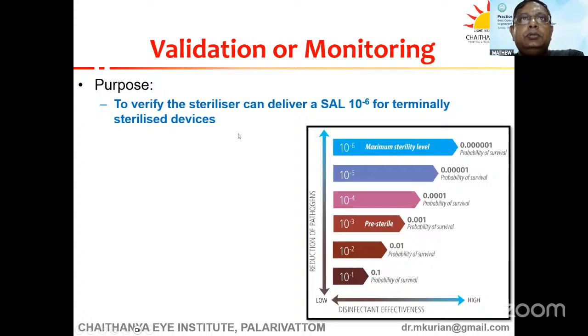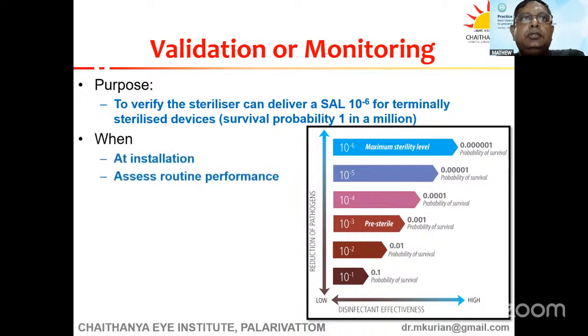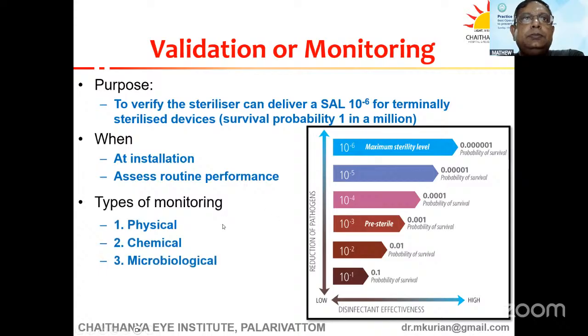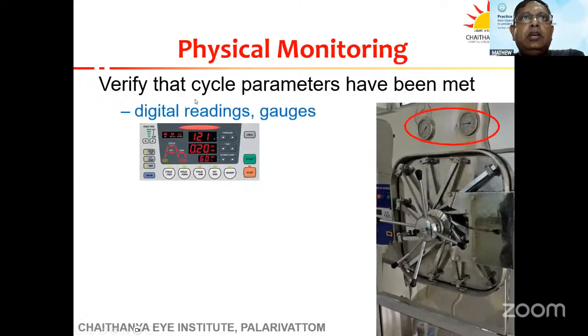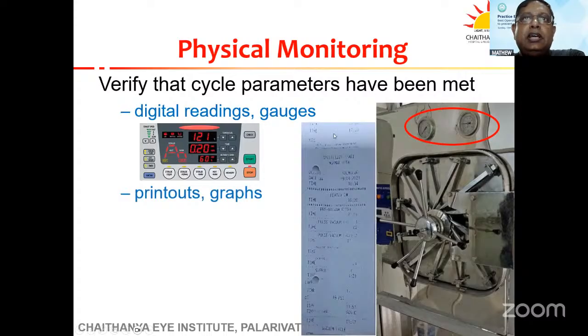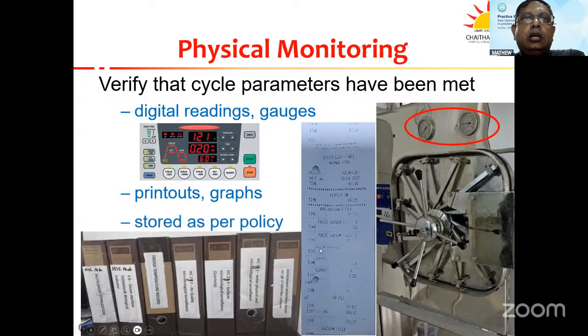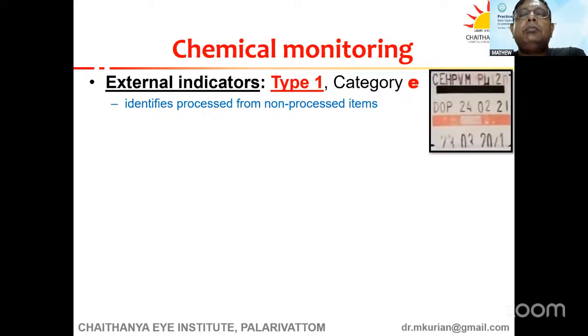In validation, what we are trying to do is to monitor that what we are hoping to do is actually achieved, and we are looking for a sterilization assurance level of 10 to the -6. That is, the probability of survival of an organism should be 1 in a million. And it should be done at installation to assess the routine performance. And this monitoring can be by physical, chemical, or microbiological methods. So in physical monitoring, we are verifying that the cycle parameters have been met. And this is by these kind of digital readings and gauges, which are present on all the devices that we use. It is desirable to have a machine which will give an automatic printout, and these printouts can then be recorded and stored rather than us writing it down. It's a better validation practice to have something which is automatically printed.